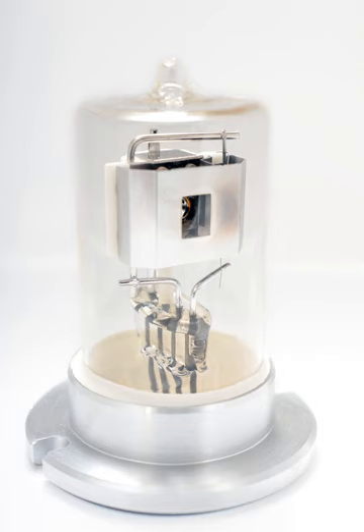The arc created excites the molecular deuterium contained within the bulb to a higher energy state. The deuterium then emits light as it transitions back to its initial state. This continuous cycle is the origin of the continuous UV radiation.